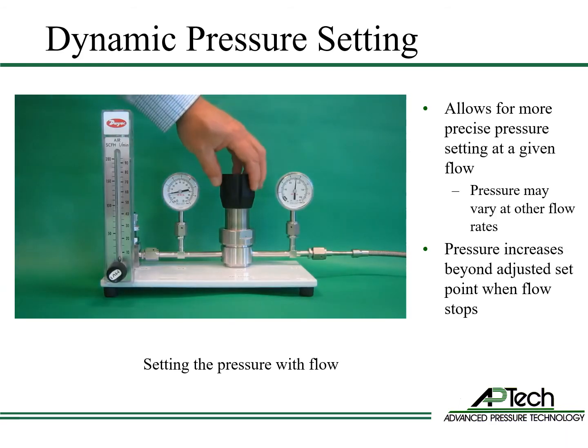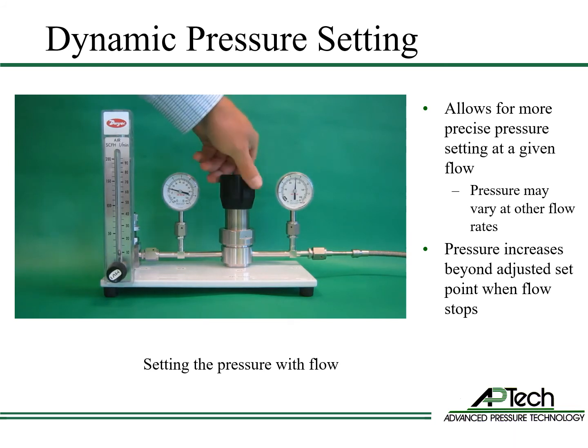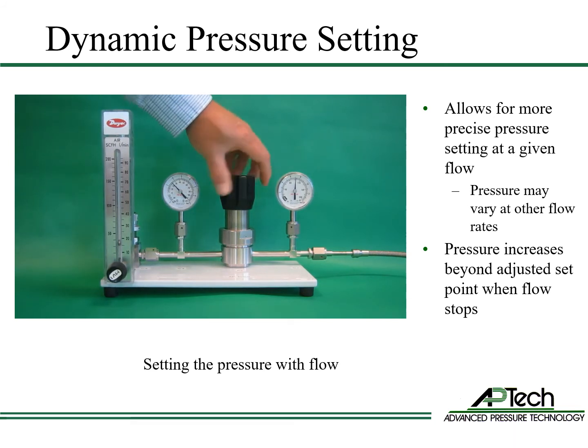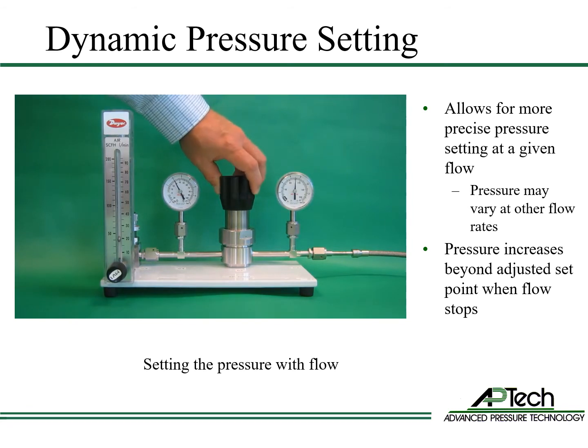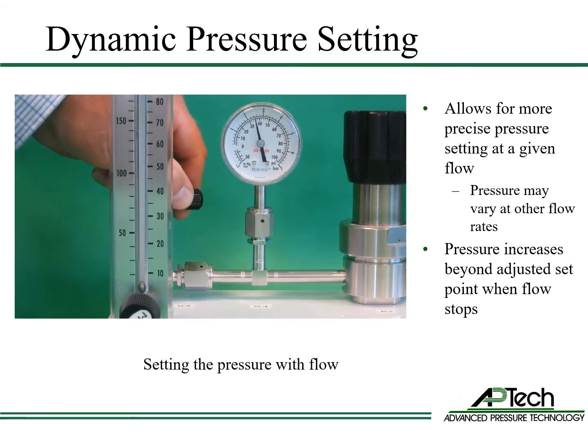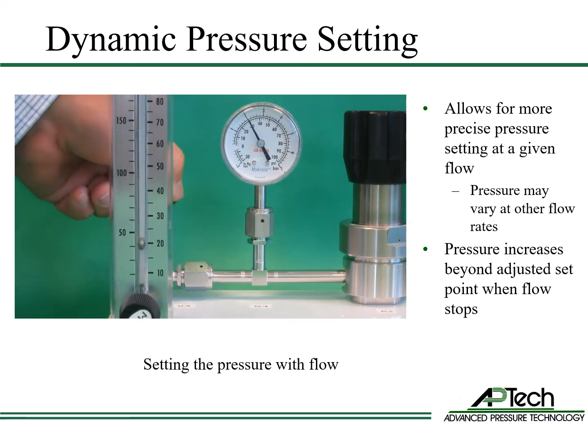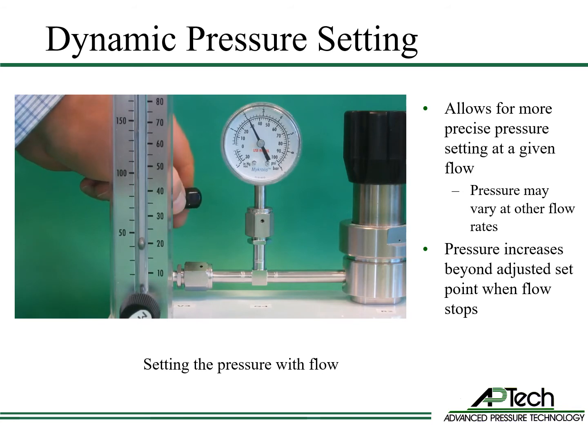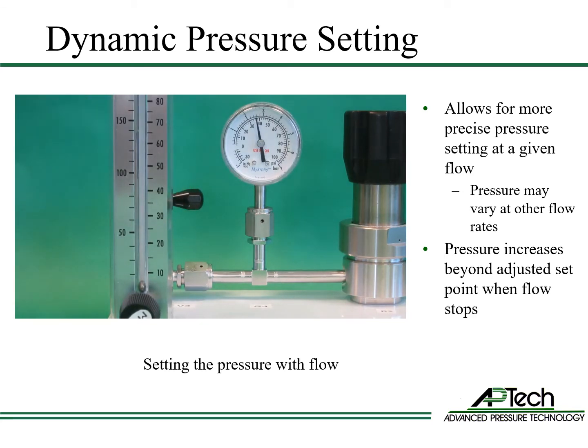Dynamic pressure setting means to set the outlet pressure with flow. This allows for a more precise pressure at a given flow. In this example, the regulator is set with a fixed flow downstream. When flow stops, the outlet pressure rises above the adjusted setpoint due to droop. If the flow rate changes later, the outlet pressure will vary.